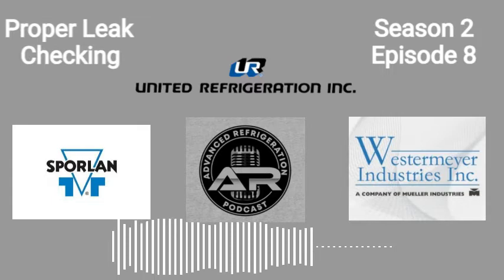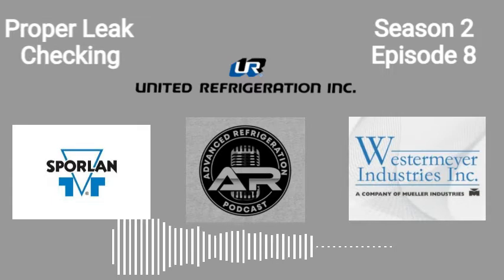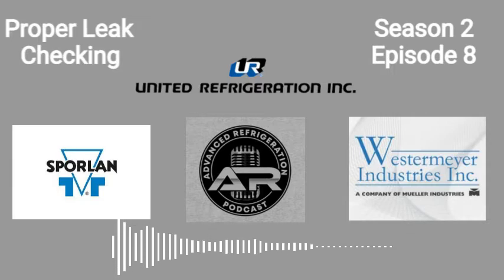But again, this is where the Stratus is king. You walk up to it, generally without even venting it out, I can tell what case it is by throwing it in PPM mode and walking the case. And as it starts going up, boom, it's in this case. I pull the bottom pan and usually I can find it. You shut off the fans? Sometimes. It depends. Hardly ever, no.